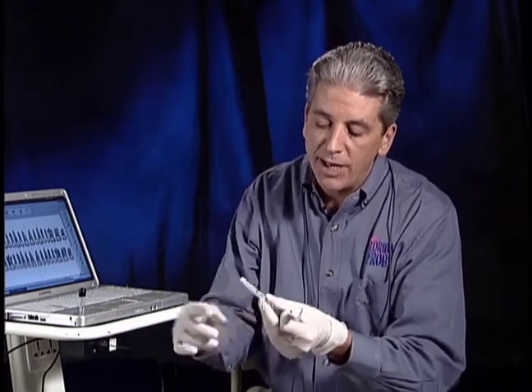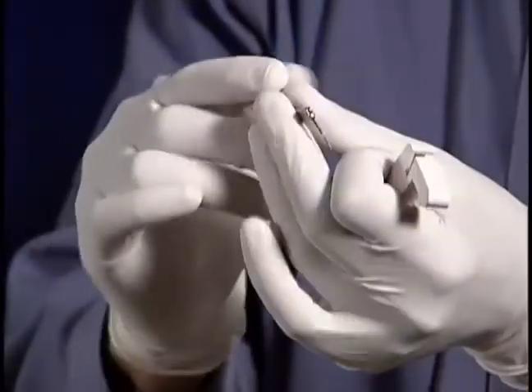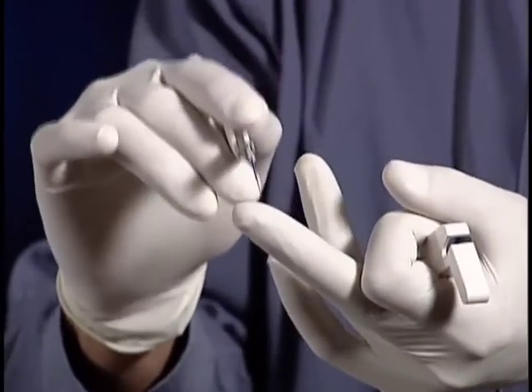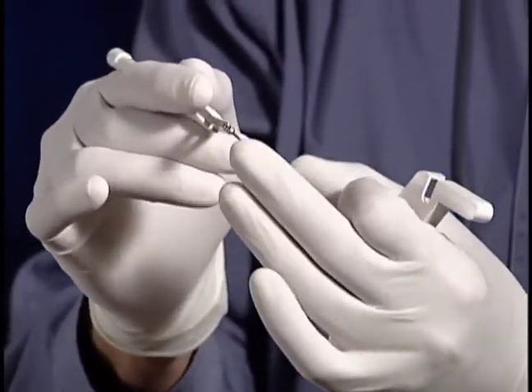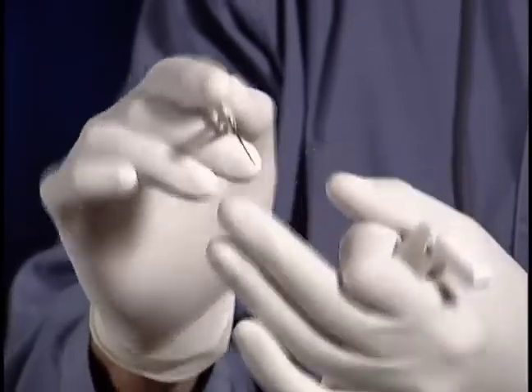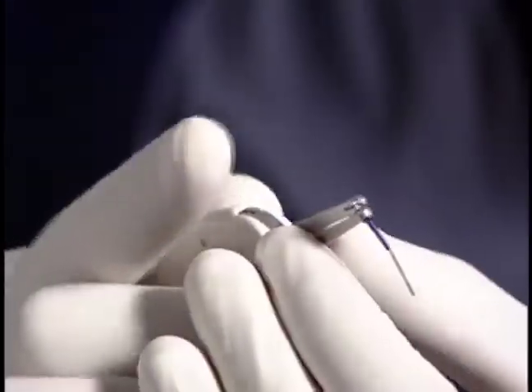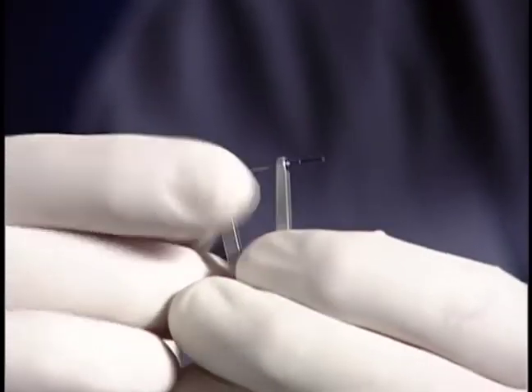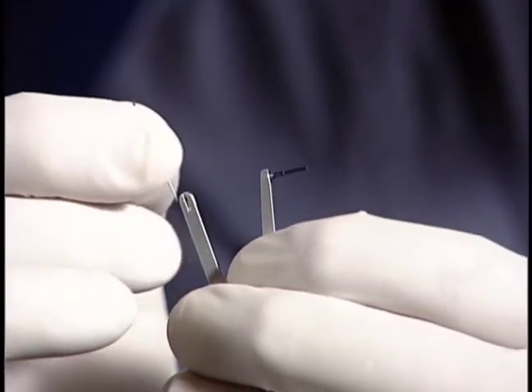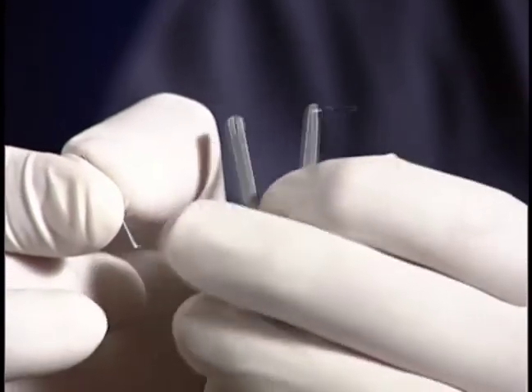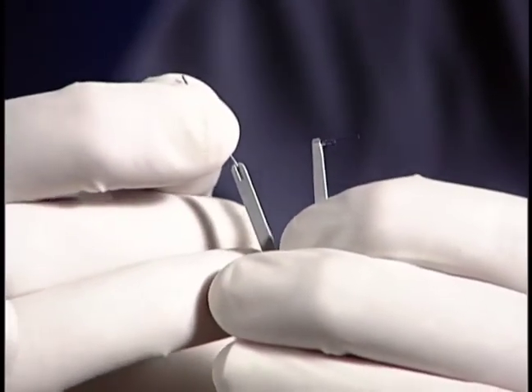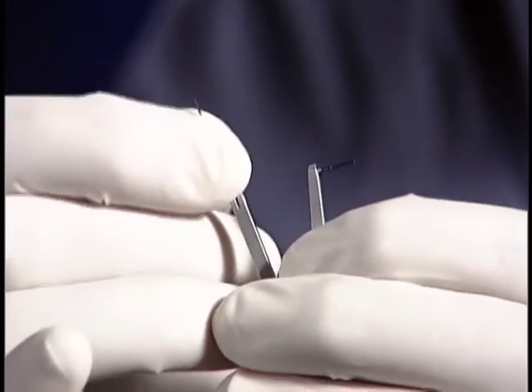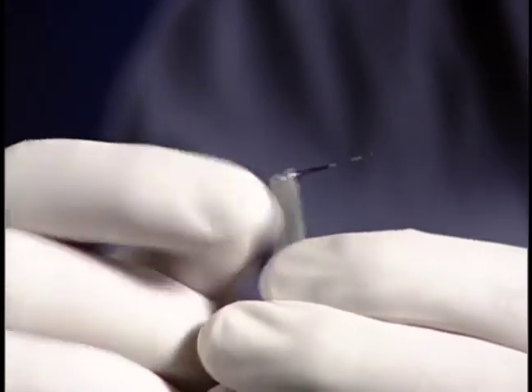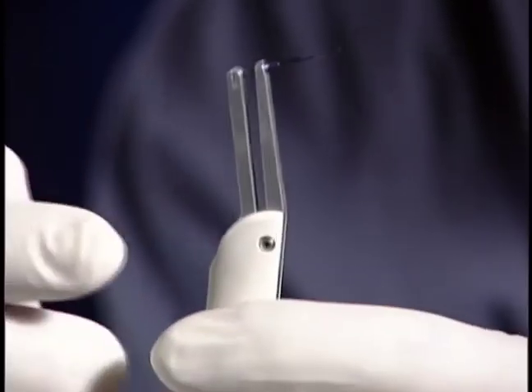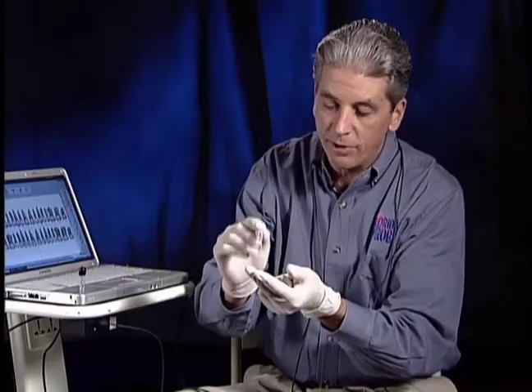The tip, the implant grade titanium tip, is replaceable but not disposable. The only reason that you would change it is if it were bent and you were not able to straighten it. It just needs to be free floating. If you need to change it, simply pull the tip through, rotate it, and this little tip goes in that slit and the opposing hole. It just needs to be free floating.